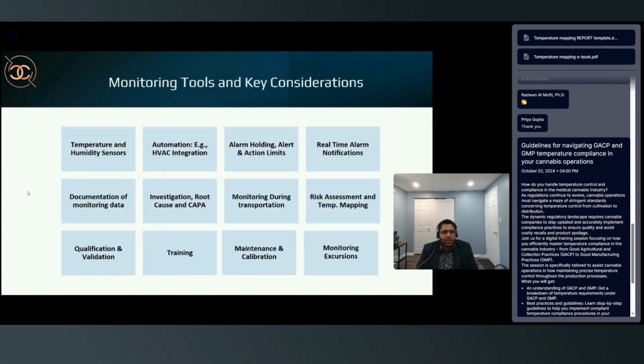Qualification and validation. I have briefly touched base on this. You have to make sure that the sensors you are obtaining, and the companies you are working with to obtain those sensors, are validated, not just the sensors in terms of getting your calibration certificate and how often you're going to calibrate. All those factors should be in place. Your SOP should be in place for that. But you're also qualifying the company as a service provider. So whether the software they have is part of GMP, you might have to validate that software before you use it, or that could be asked as part of your audit requirements. So make sure that the qualification and validation part is also covered.